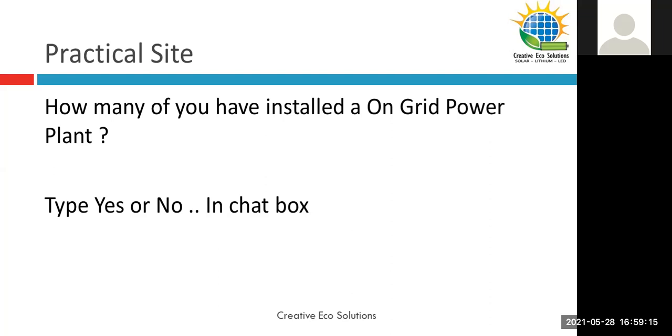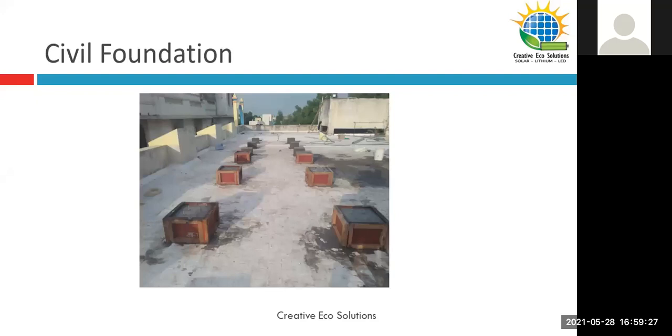The main problem was that in the area, one side was sand and another side, the substation area, was rock. So we could not make the substation at all. It took 15 days to dig for the substation. We brought a tractor and borewell drilling to drill the rock area. So that itself is a very big task. Day and night we worked. Unexpected, nobody knows what is inside.